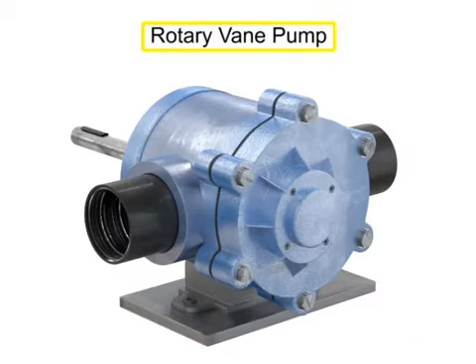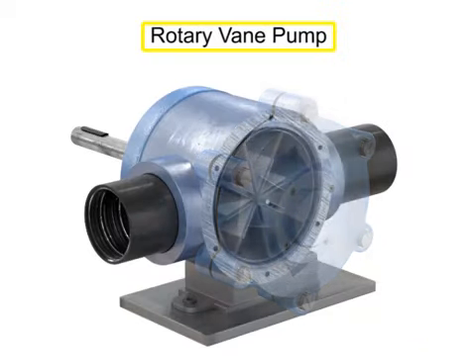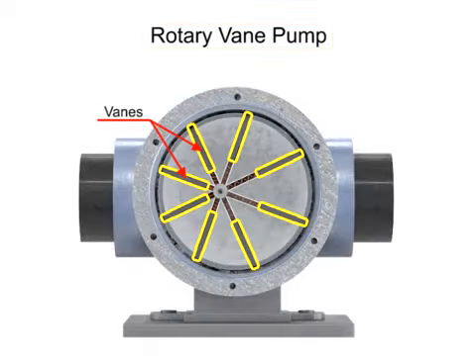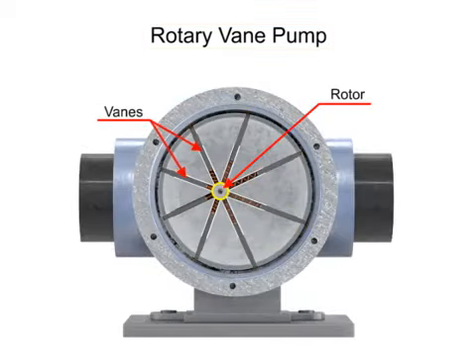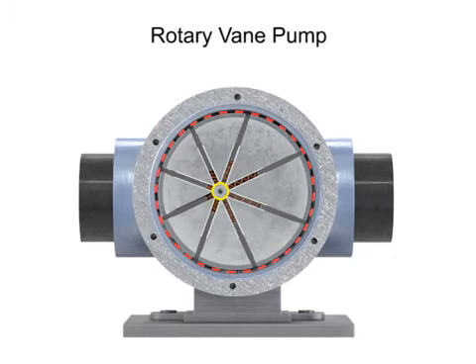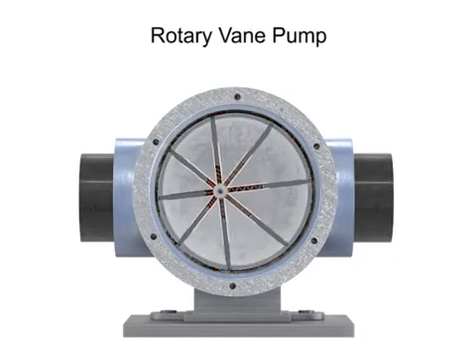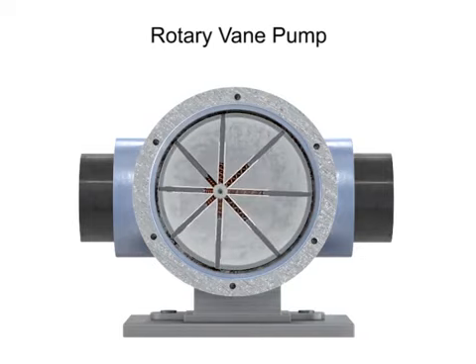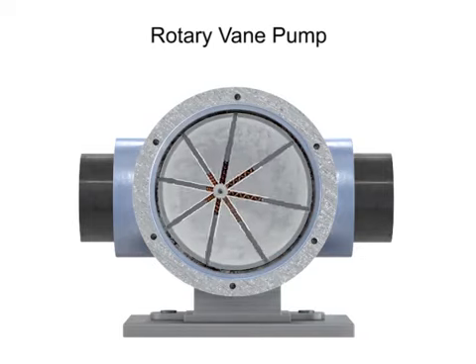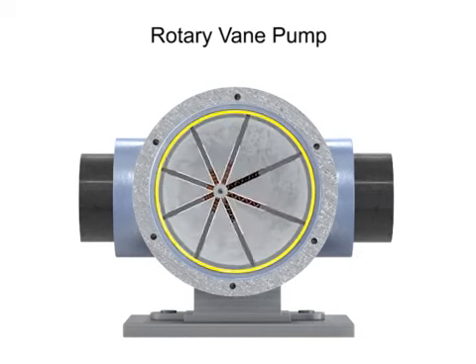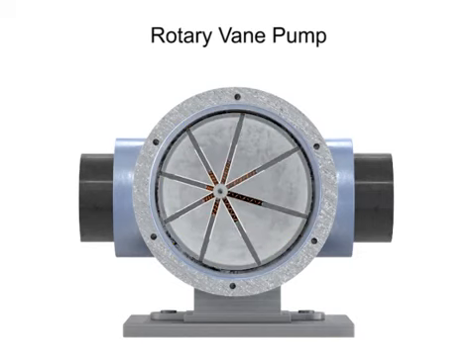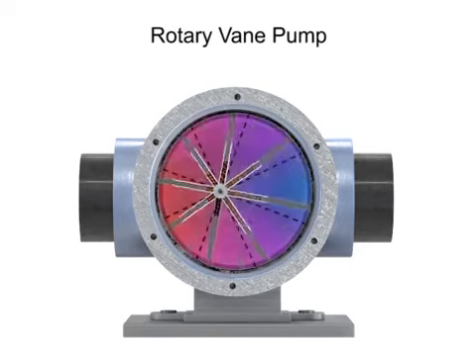A rotary vane pump is a positive displacement pump that consists of vanes mounted to a rotor. The vanes are on an off-center drive shaft. As the shaft rotates, the variable-length vanes slide in and out to maintain contact with the pump housing. The tension in the vanes is maintained by either springs or hydraulic pressure, and as the vanes rotate, they create chambers of varying sizes within the pump.